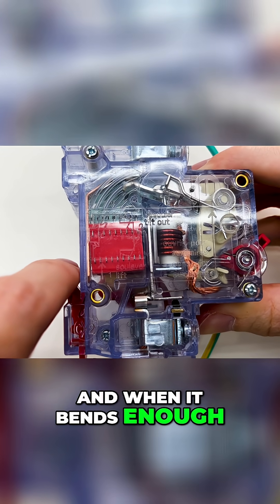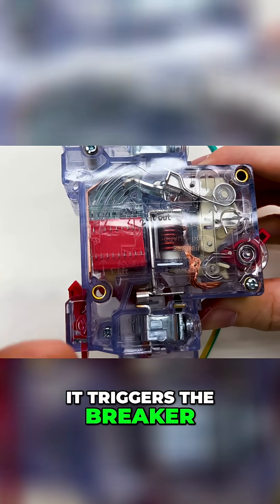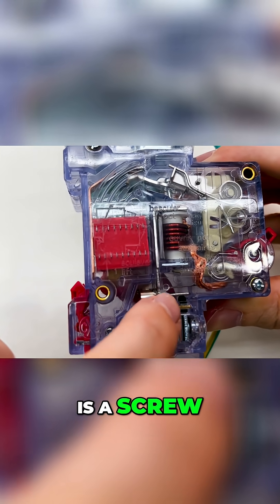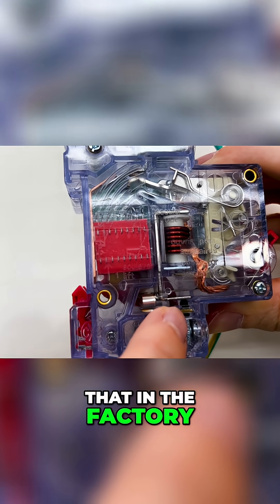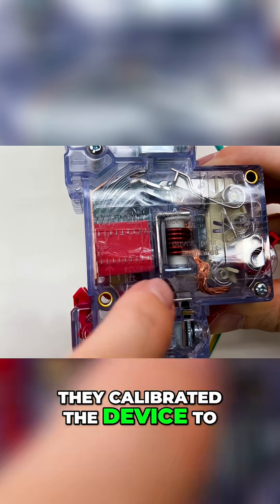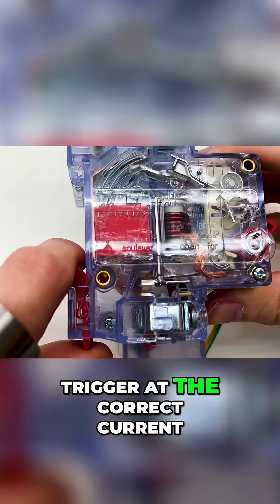And when it bends enough, it triggers the breaker. And on the bottom, you can see there is a screw that in the factory they calibrated the device to trigger at the correct current.